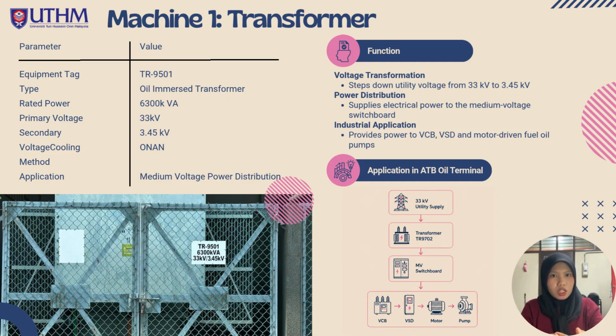For the application of this transformer in ATB, it supplies power to the medium voltage switchgear, VCB, VSD, and large pumping system used for petroleum transfer operation. Without this transformer, the electrical power received from the TNB cannot be utilized by the process equipment. So overall, this transformer is one of the most critical components in the entire electrical system because it acts as the interface between the TNB supply and the plant operation.